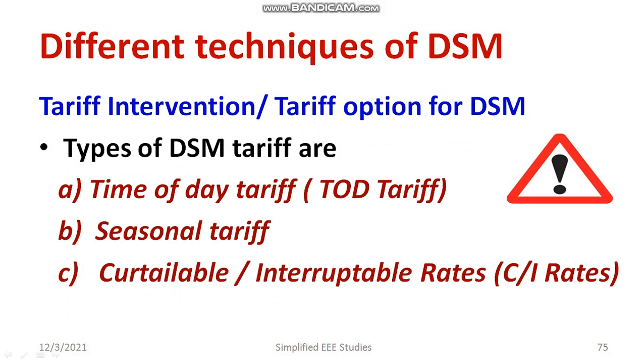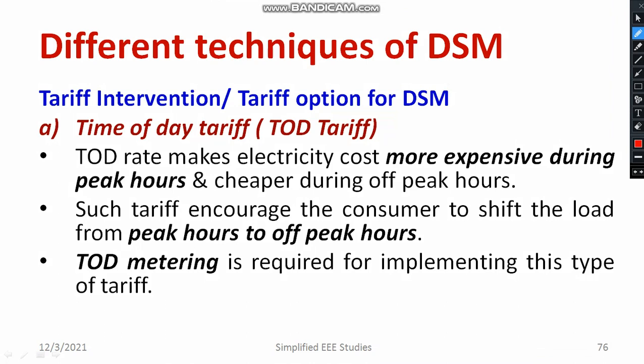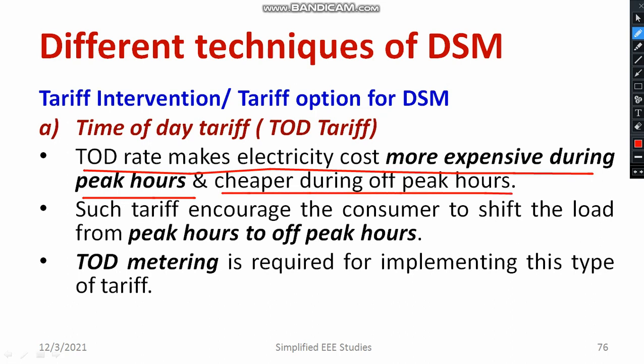Let us have a brief discussion on these three types of tariff. What is time of day tariff? The cost of electricity varies with respect to time. If you consume electricity during peak hours, you are charged more. With the help of a TOD meter, you can identify this. TOD rates make electricity cost more expensive during peak hours rather than off-peak hours, and the cost is very cheap during off-peak hours. It encourages usage of electricity during off-peak hours instead of peak hours, and customers will obviously shift their load from peak hours to off-peak hours to save cost.